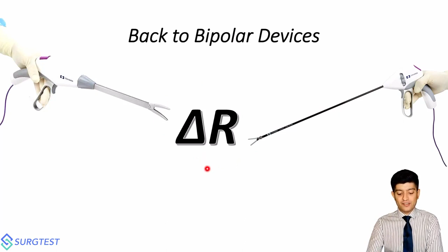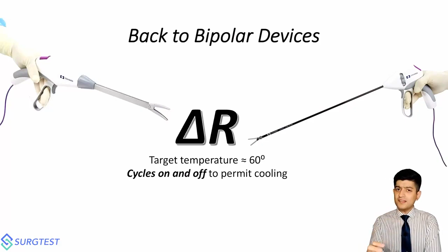What exactly are they? The first thing is there is a temperature sensor. They want to get the temperature up to 60 degrees Celsius. This, remember, once again, is the point at which instantaneous cell death occurs. So you don't have to wait 5 minutes for cell death. You can't keep applying energy for that long. They want the temperature to get to around 60 to 80 degrees Celsius. So when it reaches that preset temperature, but say the change in resistance has not reached where it needs to be, it shuts off the energy, allows the tissues to cool, and once they are cool, it refires them. All of this happens within split seconds.